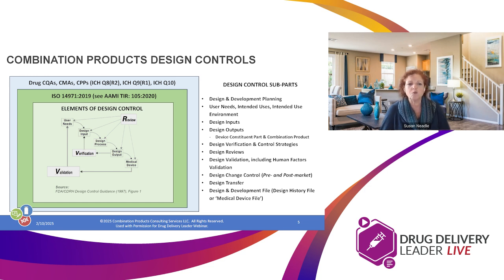So in that context, knowing that the drug is my focus, I still have to worry about my device constituent part. And that device constituent part is built on a foundation, again, of risk management. And here you could look at AAMI TIR 105 from 2020. That particular technical information report is called Combination Products Risk Management, and it talks about the integration of ISO 14971 with ICH Q9(R1).